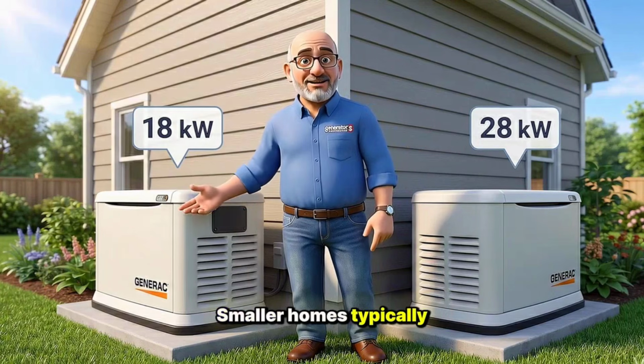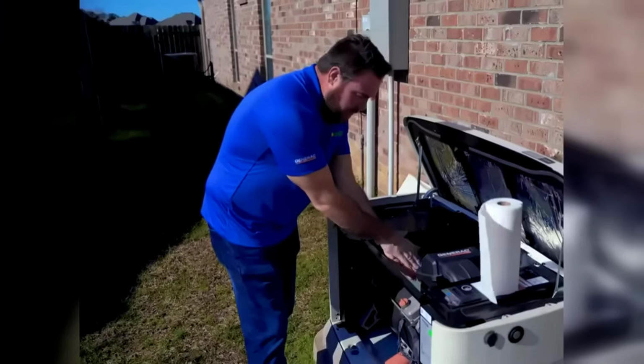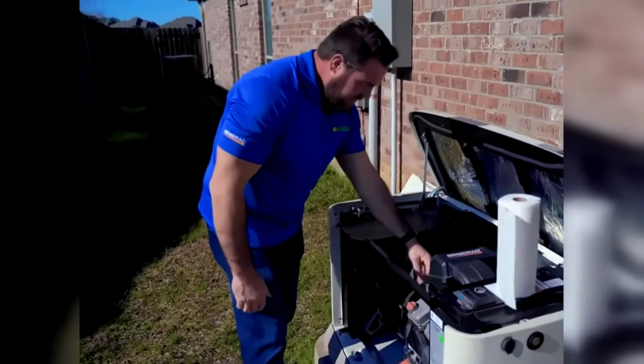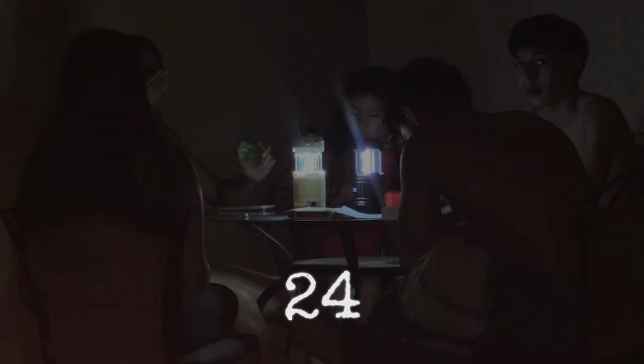But because the system is marketed as fully automatic, nobody tells the homeowner that they actually need to babysit the machine. If you do not go out into the freezing rain or extreme heat, open the heavy metal cabinet, manually check the dipstick, and top off the oil every 12 to 24 hours, you're going to hit a wall.